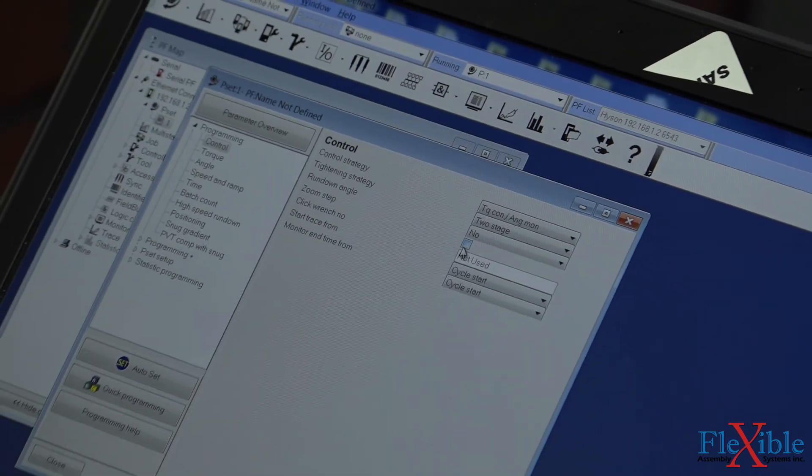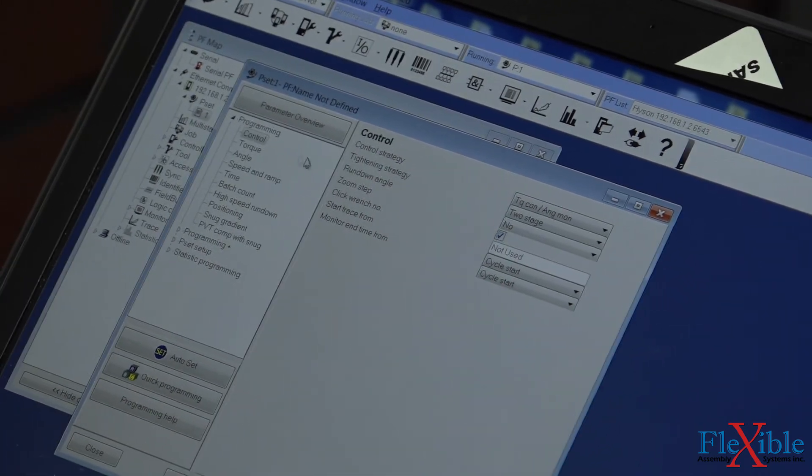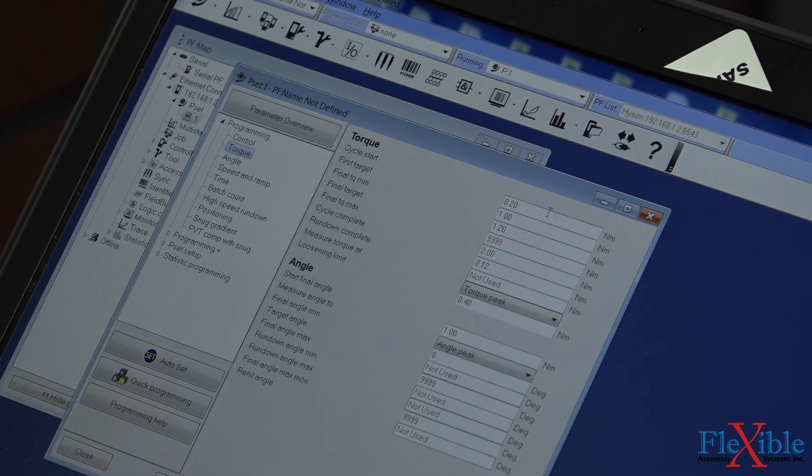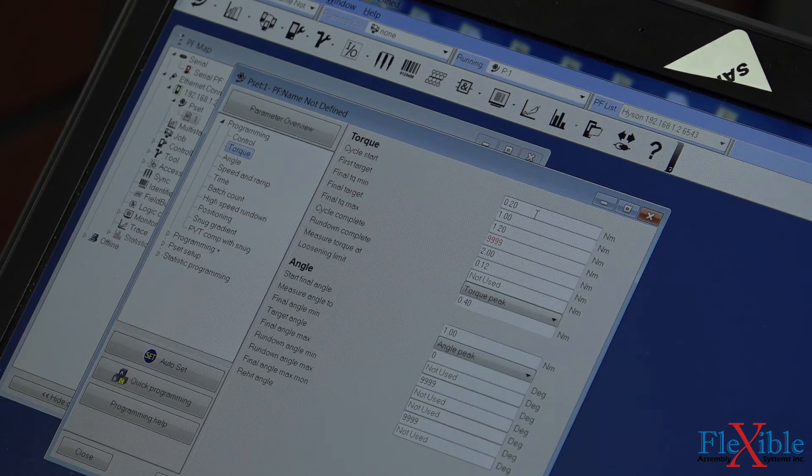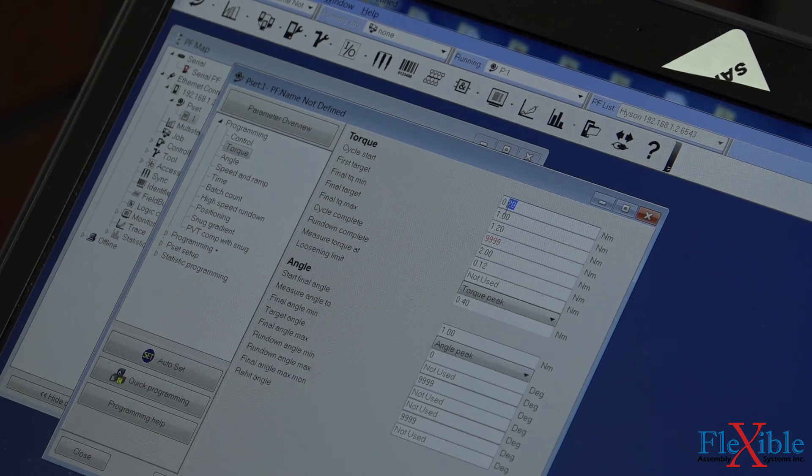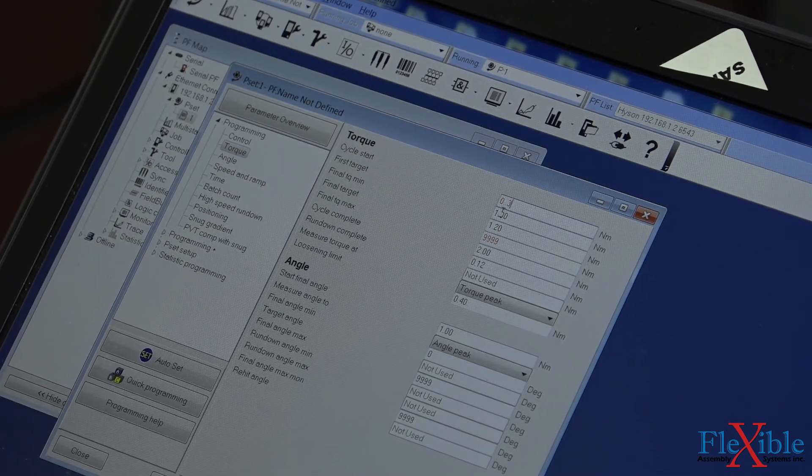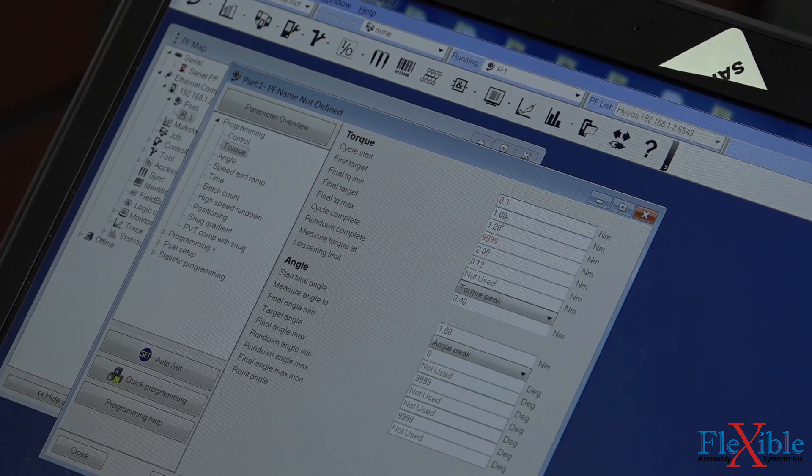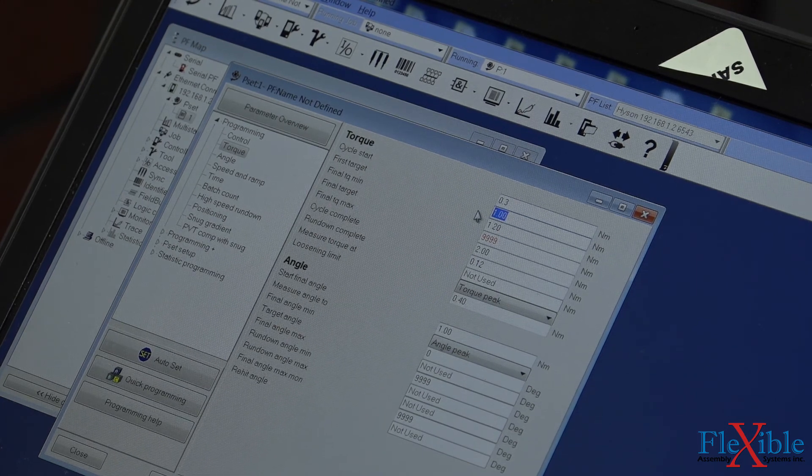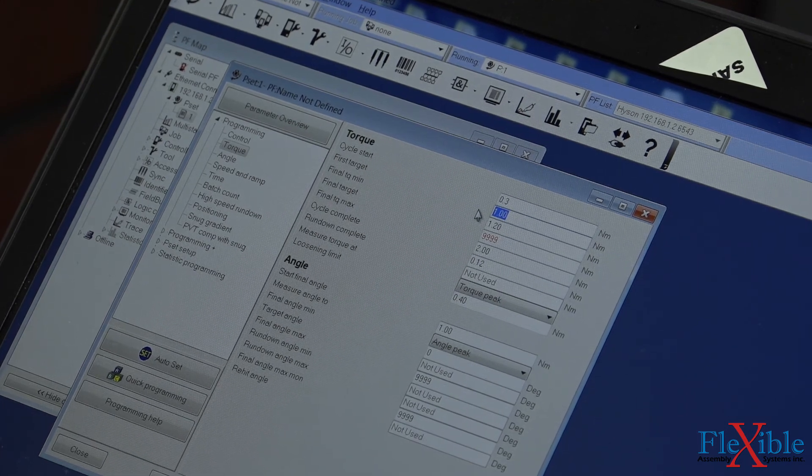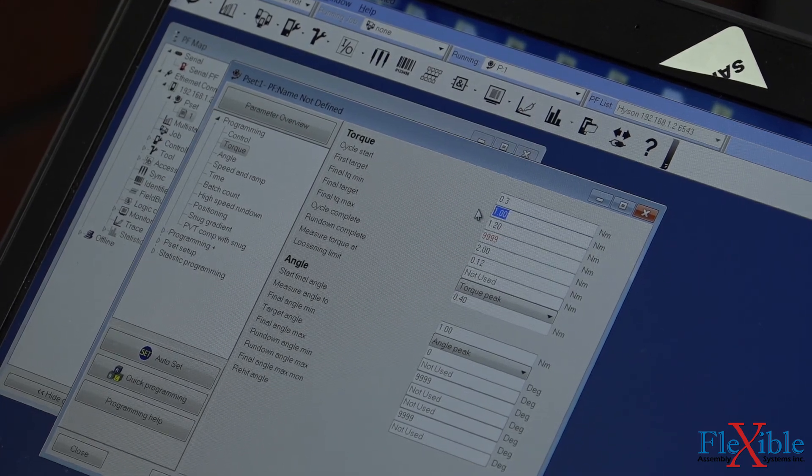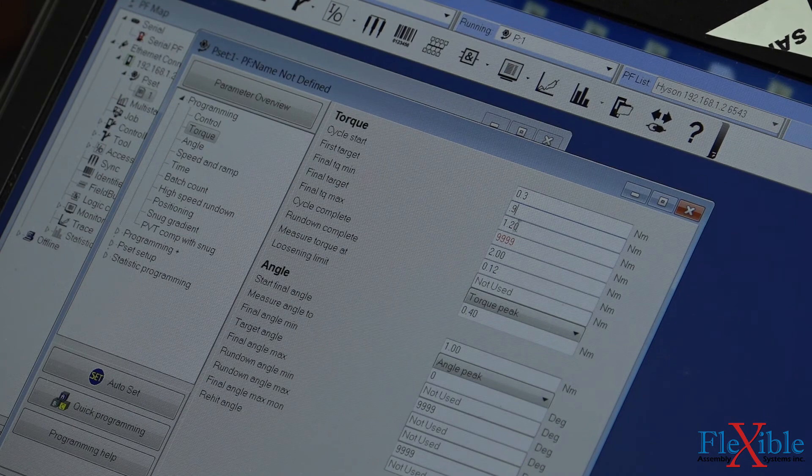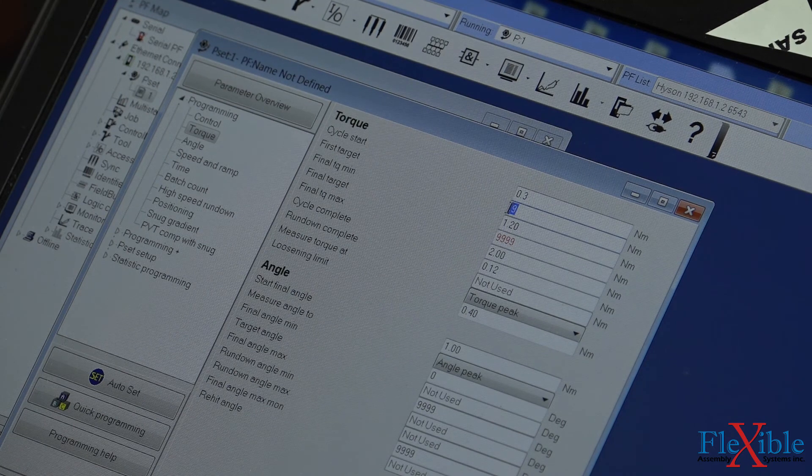We are using a 1Nm transducer, so we will aim for 0.9Nm as our final target. Since we are using a power tool with a soft joint, we will need to do some tests to see how the joint will react. We set our first target to 0.4Nm to start. We changed it from 0.5 off camera.